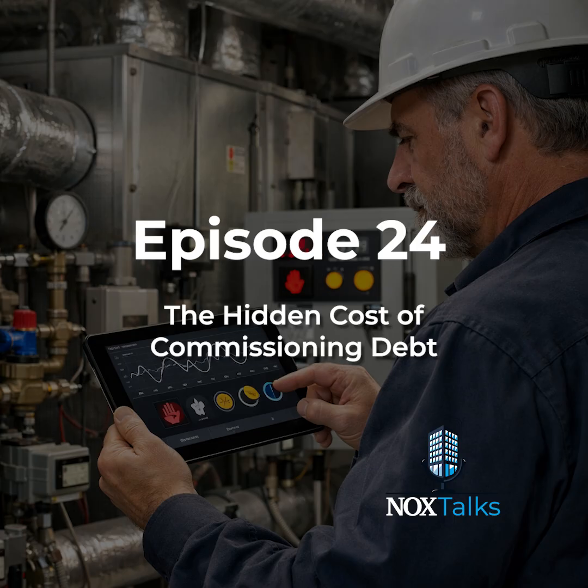And here's the problem. The market loves to jump straight to AI, dashboards, and portfolio analytics. But if the air handler is hunting, or the VAV boxes are reheating against cooling, all that shiny software is basically reporting on chaos. It's not that analytics are bad, it's that analytics can't rescue a building from bad fundamentals. Bad BAS data just gives you a more expensive way to rediscover the same old comfort calls. That's why this matters right now.